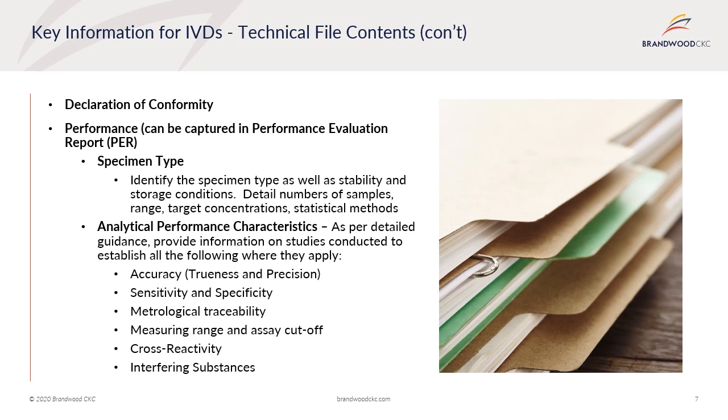So your specimen type needs to show the equivalence between those, as well as any of the potential ranges for the analyte that you're looking for, and maybe storage conditions, or specifically, are you using EDTA, heparin, citrate? So the specimen type becomes extremely valuable and needs to be proven so that not only can you say that your intended use specimen is met, but any of the supporting data and the specimens used to create that supporting data are there.